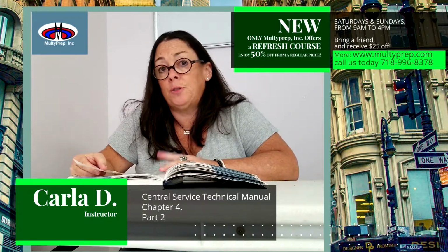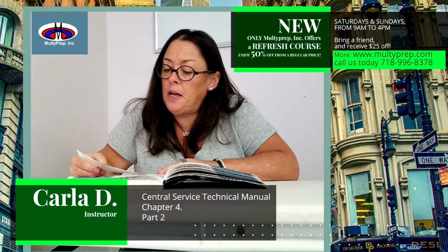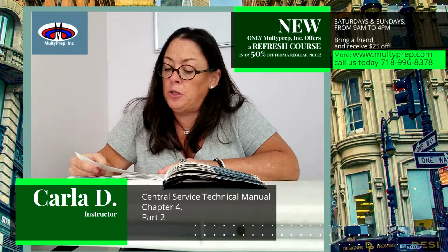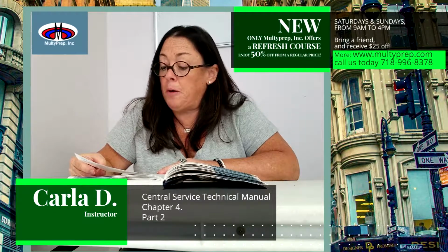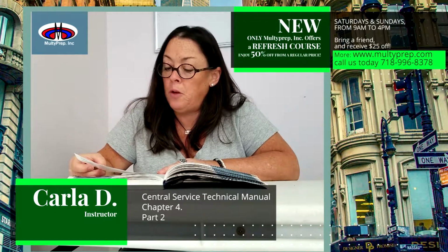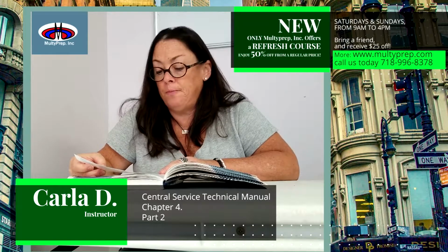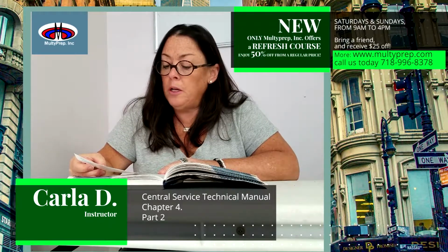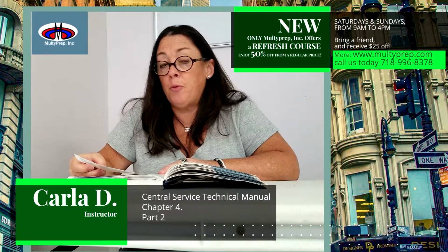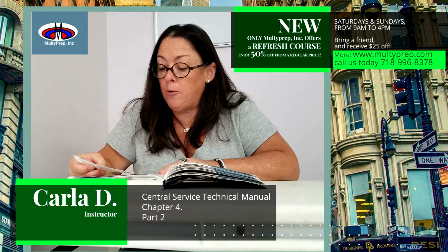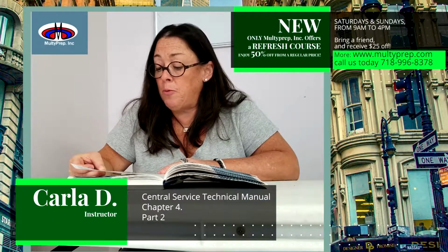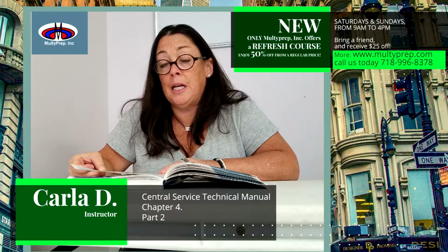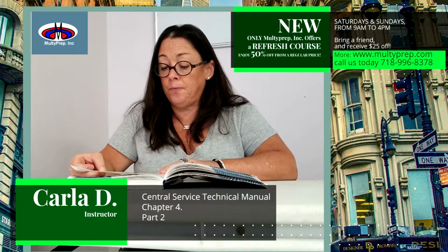A common question: you receive a case cart from the operating room to the decontamination area with a note stating instruments are contaminated with hepatitis B or MRSA. How will you handle the instruments? Answer: all instruments, except those contaminated with prions, are to be cleaned following the manufacturer's instructions and the facility's cleaning procedures. Items contaminated with prions have special cleaning and handling requirements.